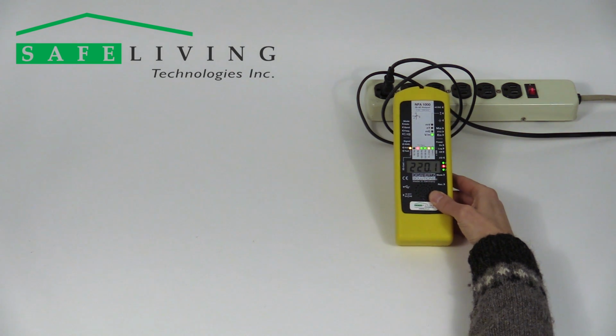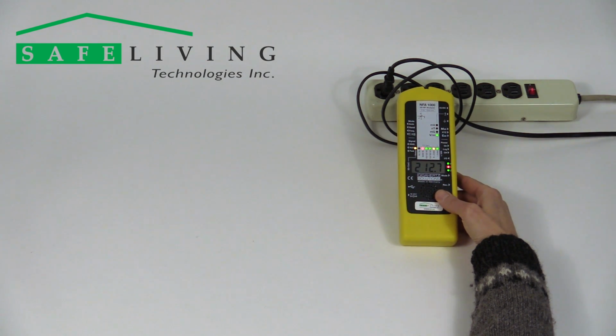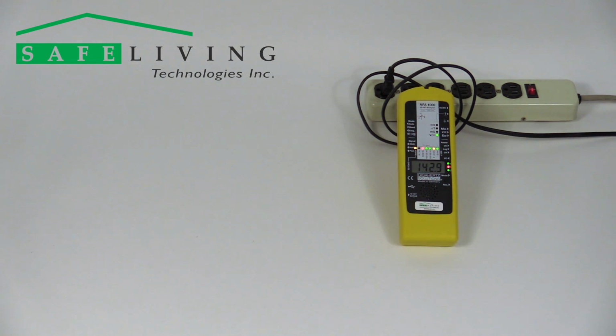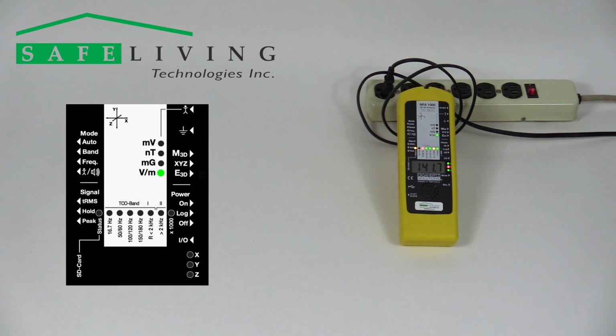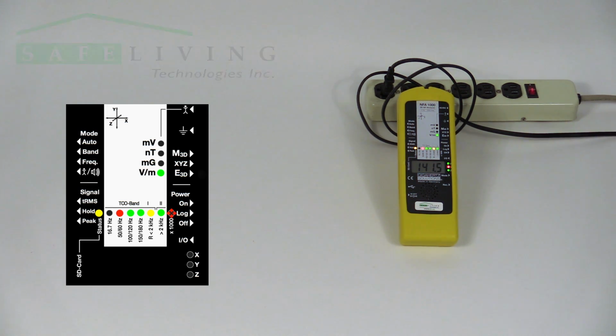The Geiger counter tone will also increase closer to the source. Now that we have found the area of concern, we can take a closer look at the meter. This time, the X, Y, and Z axis LEDs show which axis contains the strongest measured electric field with a red LED. And the frequency LEDs show which frequency ranges contain the primary and secondary levels of radiation. If the levels exceed the maximum 1,999 volts per meter, the red times 1000 LED will flash.